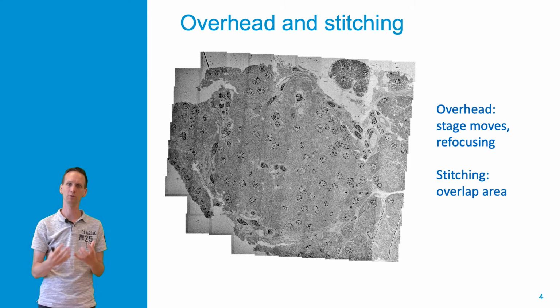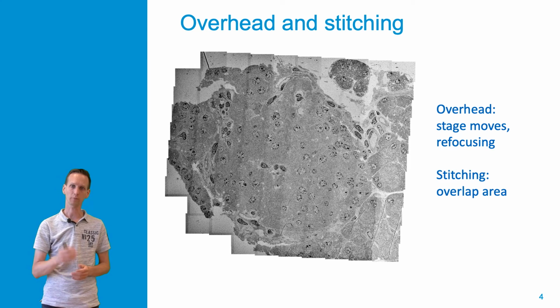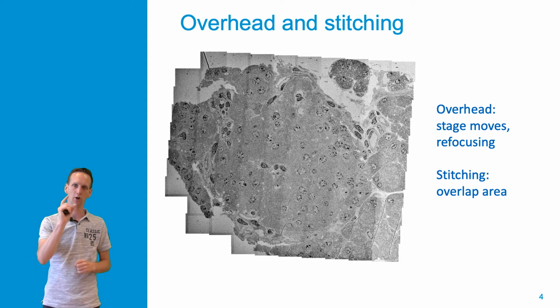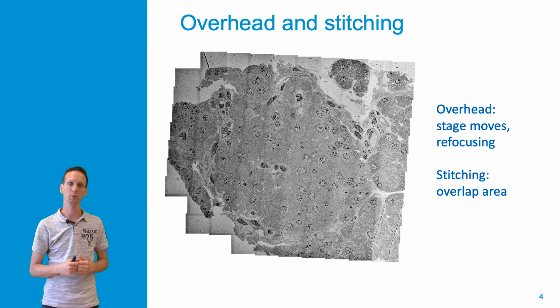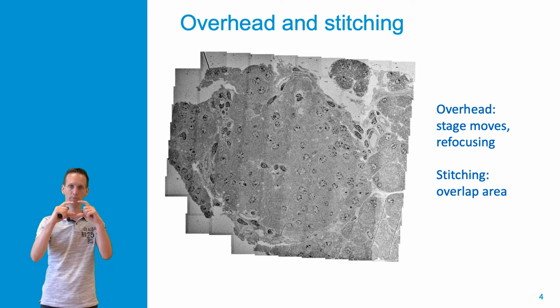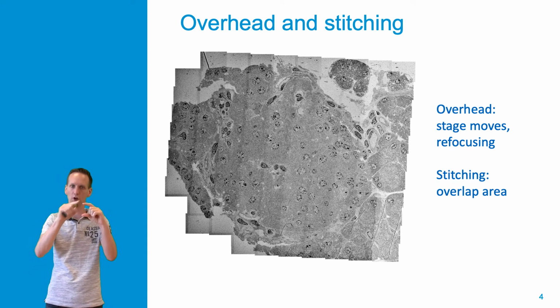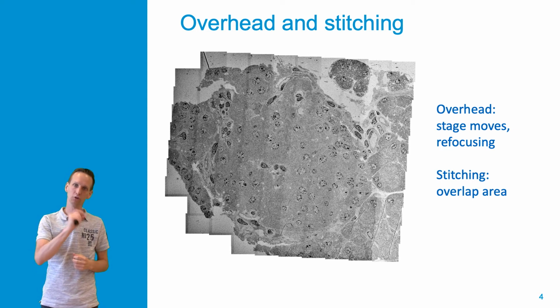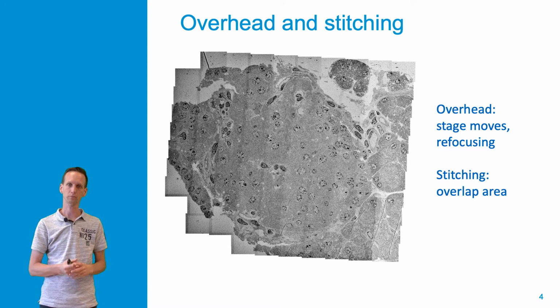Now, people have also attempted to go to three-dimensional imaging. And there are in general 2 approaches that we can take here. We've seen that the process of sample preparation for electron microscopy involves sectioning a larger block of sample. If we section that block and collect the first section, then the second section, and each following section in serial order, and scan those with reference to the order in which they are scanned, then we could reconstruct the 3-dimensional image afterwards from all the individual 2-dimensional tiles. That's one approach. This approach we call serial sections.